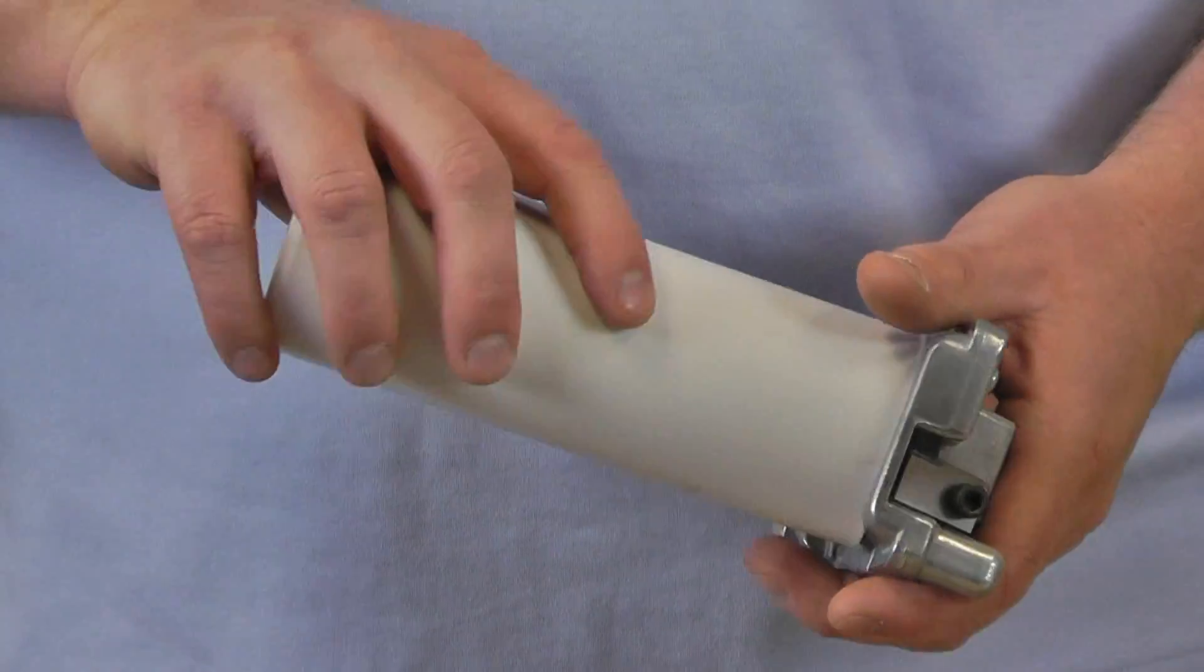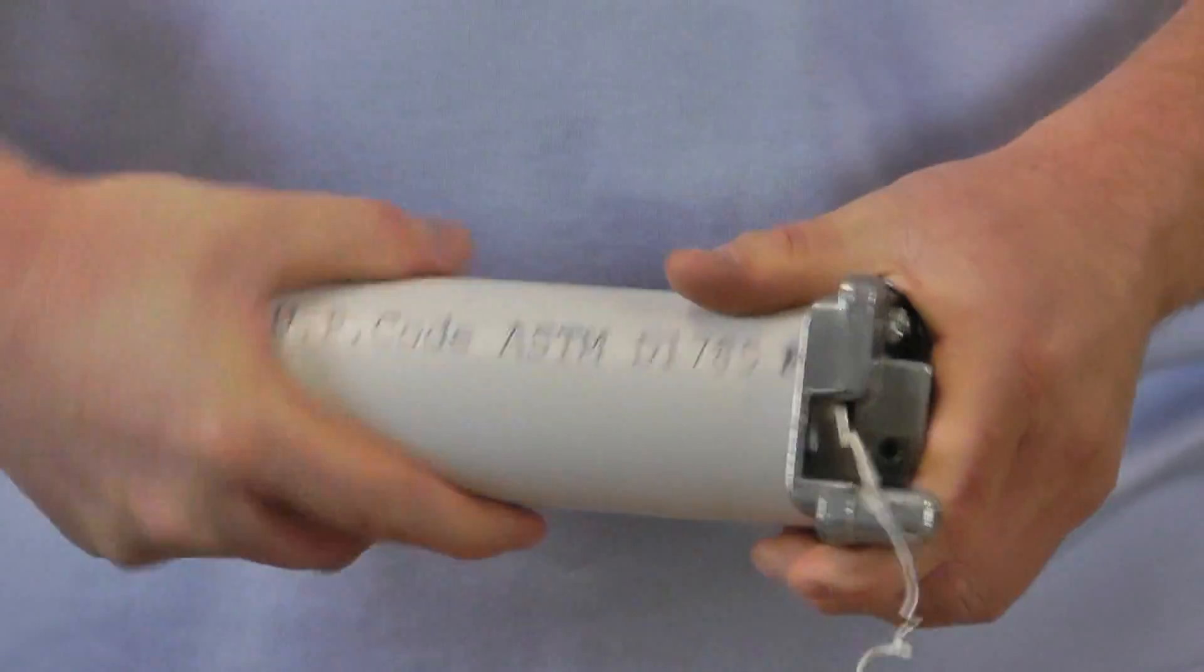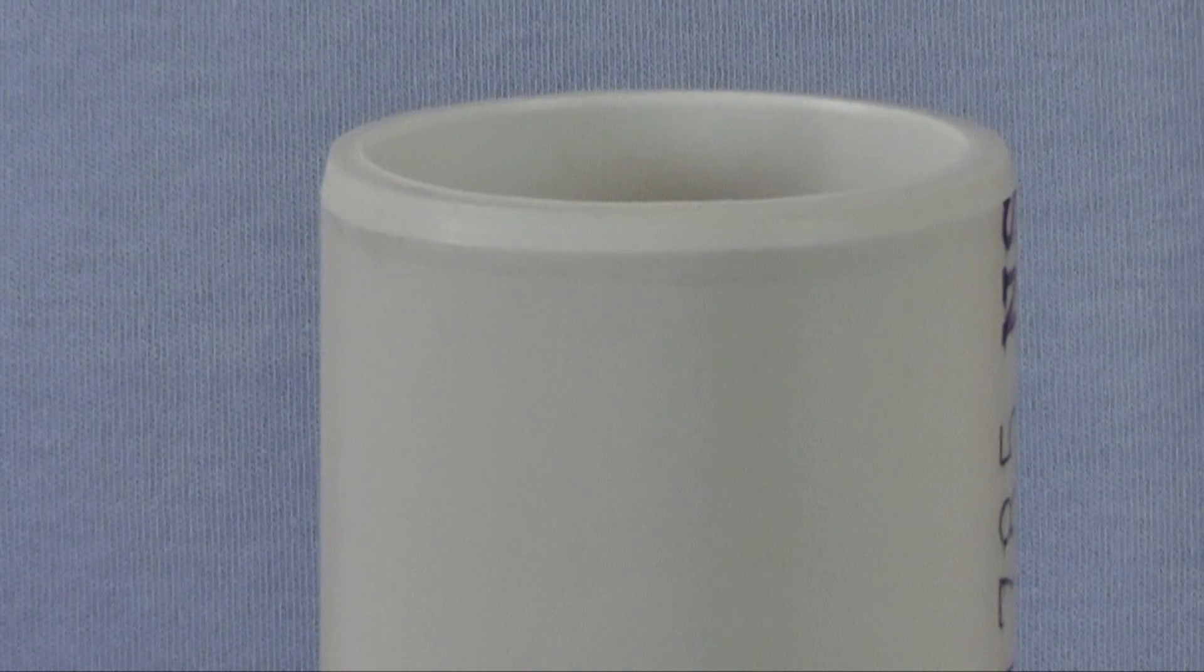Once the pipe is cut squarely, make a 10 to 15 degree bevel around the cut using the beveling tool. This can also be accomplished by carefully working a file around the outside diameter of the cut surface.